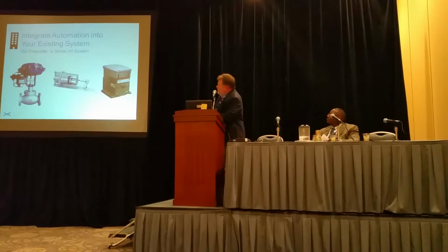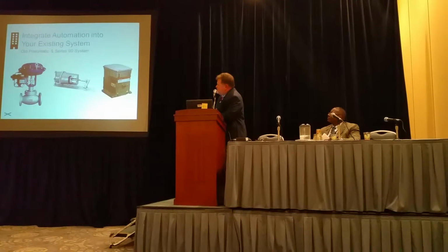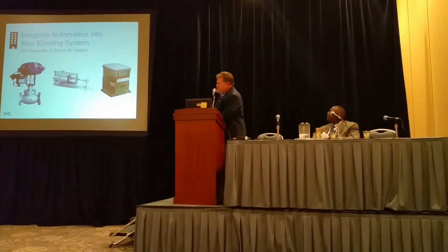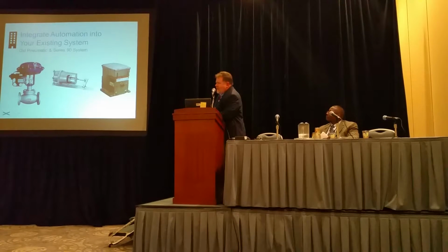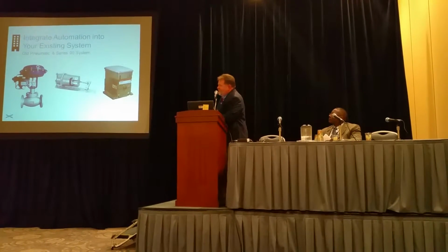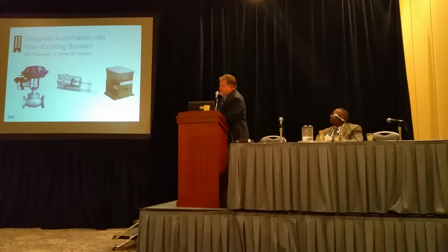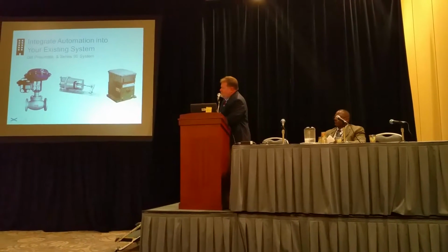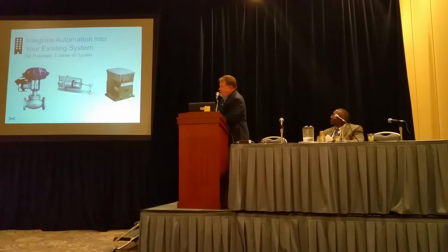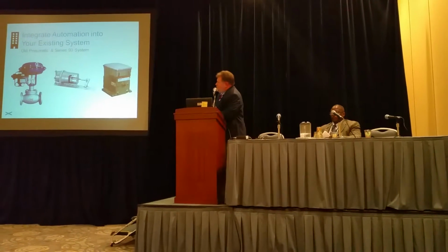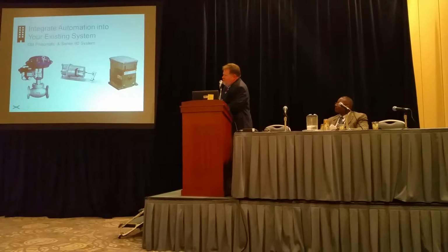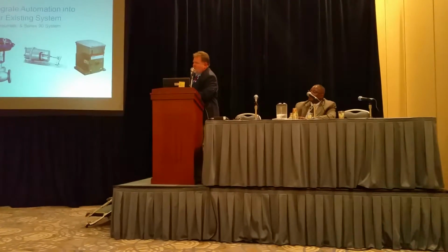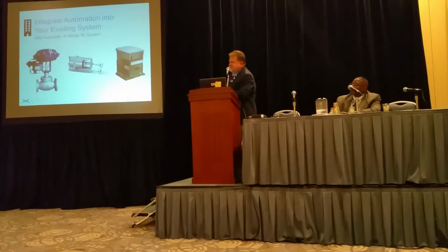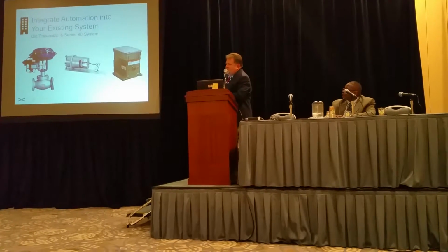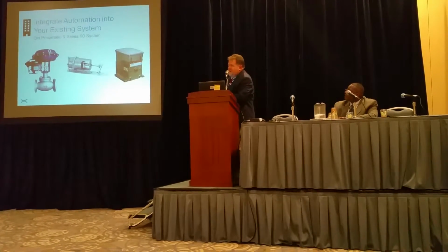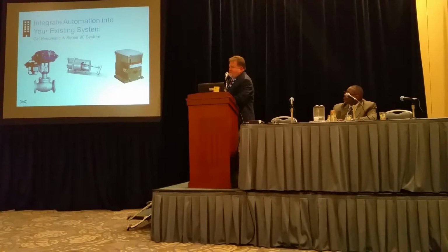So right here, these are pneumatic actuators. The first one is a pneumatic valve actuator. That's a big valve, about a 6-inch valve. It has a big diaphragm on it to open and close that valve. And to replace that, it's in the thousands of dollars. So if I wanted to put in a digital valve or digital actuator, that would be awfully costly to replace. The one far on the right is an old Series 90 control. This is commonly used for dampers and or valves. Series 90 control was a proportional signal that would open and close it. To replace that Series 90 control is very expensive.